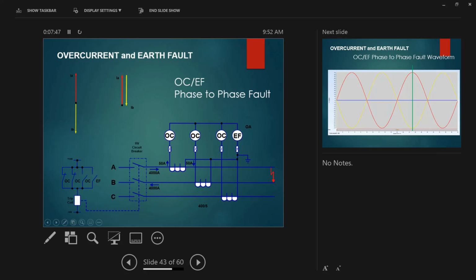So there will be no earth fault happening because you see this behavior here, opposite to each other, 180 degrees. That's like with a clamp meter. You have a single phase load. You clamp the two together, 0, because they're opposing each other. It's a single phase load. But if you separate them and you clamp only one leg of that single phase load, you get some reading because they're not opposing each other. Yeah, hopefully it's a bit clear, but that's how it goes.